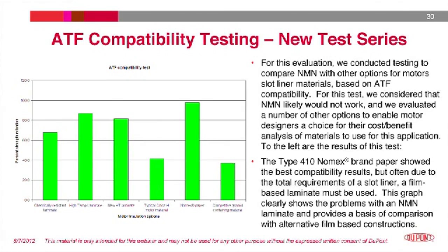Nomex paper has the best chemical compatibility of the materials tested, but it doesn't always meet the mechanical requirements for the motor manufacturer. For certain types of designs, the addition of a film in laminate form provides more stiffness and initial tear strength needed for the manufacturing process. However, the best technical solutions tend to not always be the optimum choice. With the exclusion of the cost-effective polyester film from the options for this application, credible technical data can be developed based on DuPont testing, which then helps the designers make the correct cost-benefit analysis.